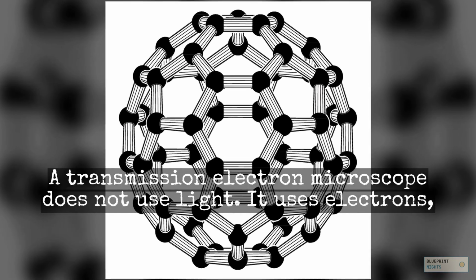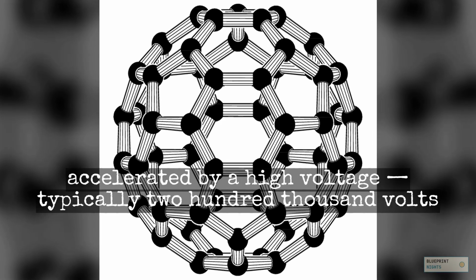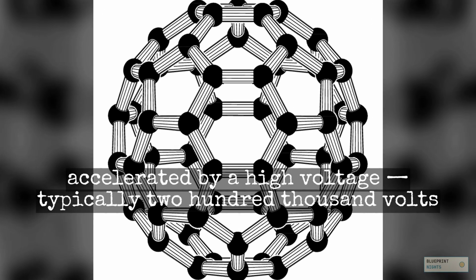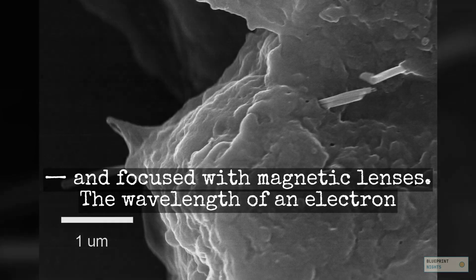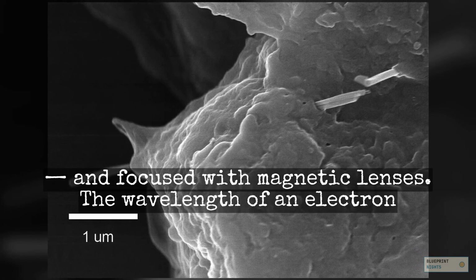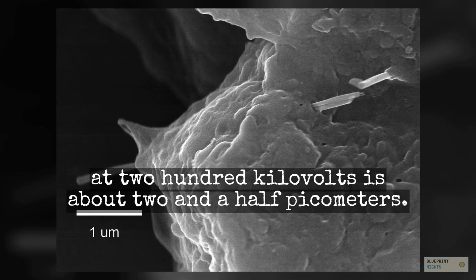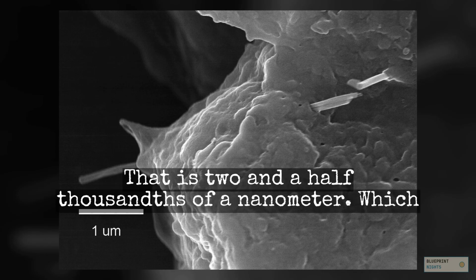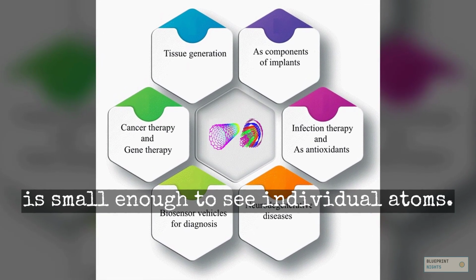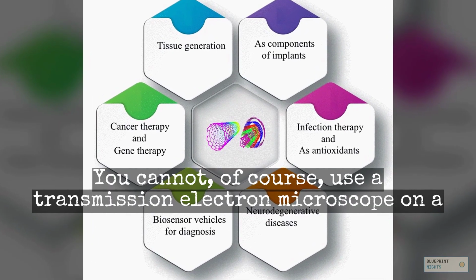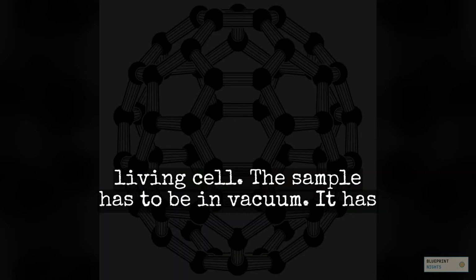A transmission electron microscope does not use light. It uses electrons accelerated by a high voltage, typically 200,000 volts, and focused with magnetic lenses. The wavelength of an electron at 200 kilovolts is about 2.5 picometers. That is 2.5 thousandths of a nanometer. You cannot, of course, use a transmission electron microscope on a living cell.